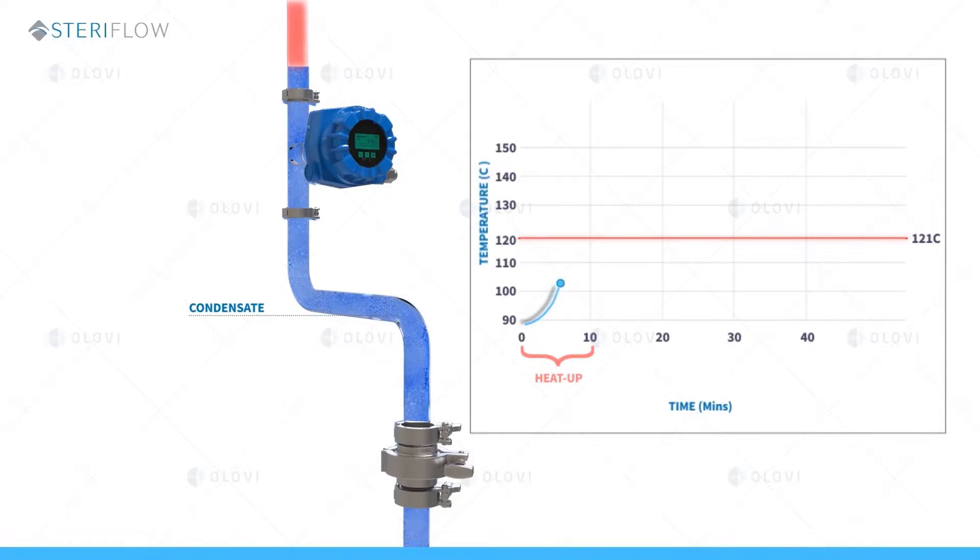As the system heats up closer to 121°C, less steam is required and the amount of condensate produced lessens. Heat up ends when the system temperature reaches 121°C, which coincides with the condensate levels falling below the level of the temperature sensor.